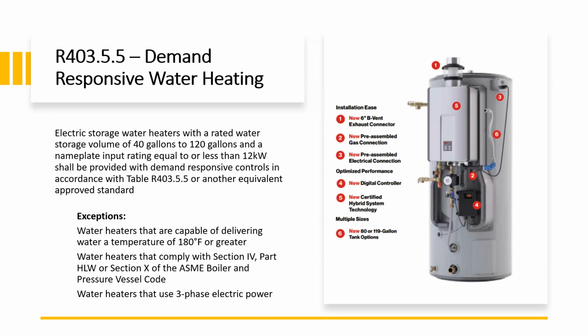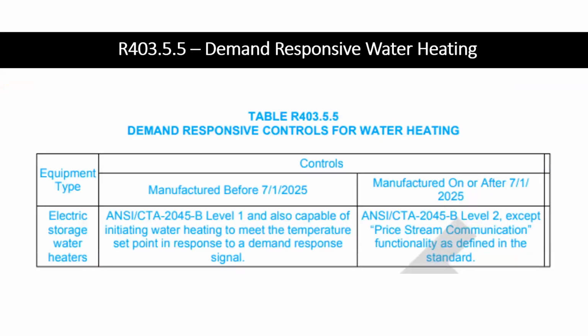This is a picture of a water heater online that I've not really seen. It looks like a tankless tied to a tank, so I'm not sure, but that's got some demand responsive controls in it. This is what the table looks like. They actually look at it by equipment type. If it's manufactured before July 1st of 2025, and then if it's after July 1st of 2025, you've got different levels of what it should meet. So different standards. There's level 1 and level 2. And as you see on level 2, it's talking about exempt, except for the price stream communication functionality for that part of it.